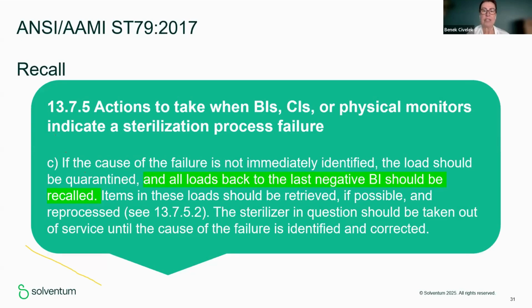ST79 is a very important reference globally. Although it's AAMI, we are also utilizing it in Europe, Middle East, and Africa. It tells about all the details of steam sterilization, and there is a very important section, 13.7.5, which covers what actions to take when the sterilization fails. Whenever you have a positive BI, it clearly states that all loads back to the last negative BI should be recalled. So if you are performing the best practice of every load monitoring, for you it will be the last cycle. So every load monitoring is also of great importance here when it comes to sterilization process failures.